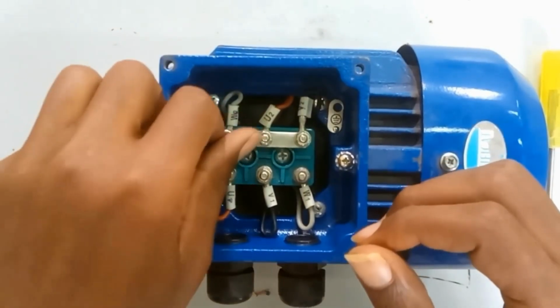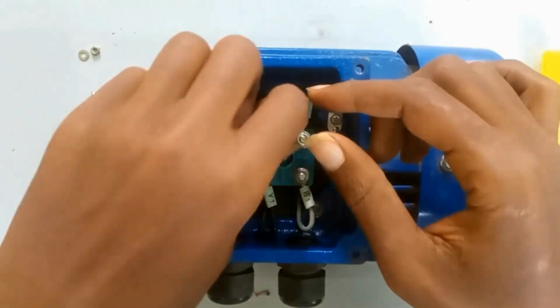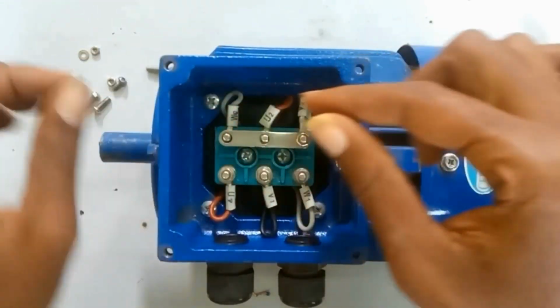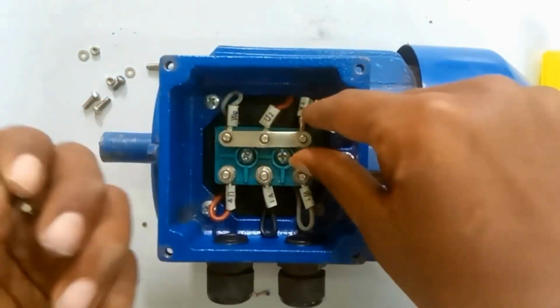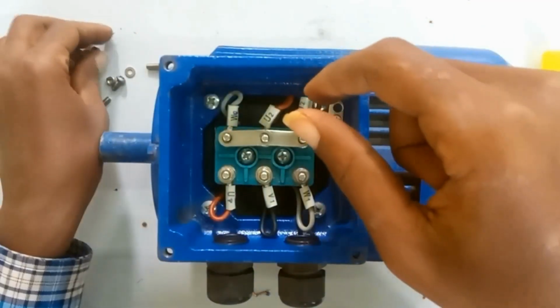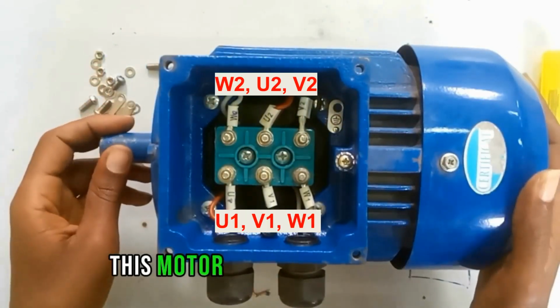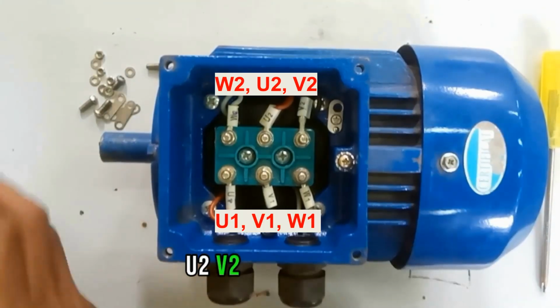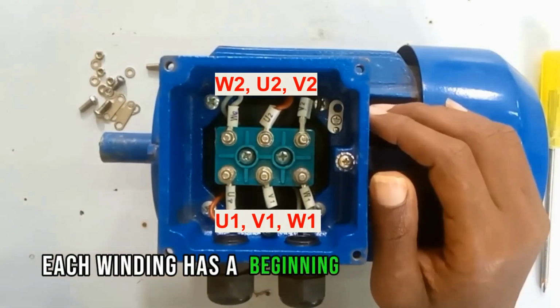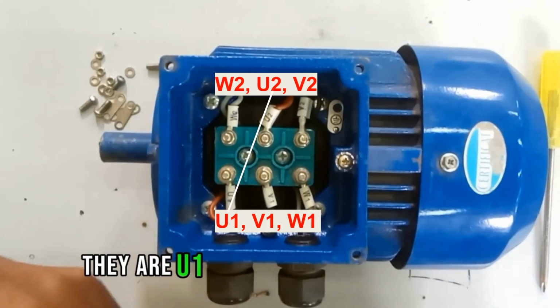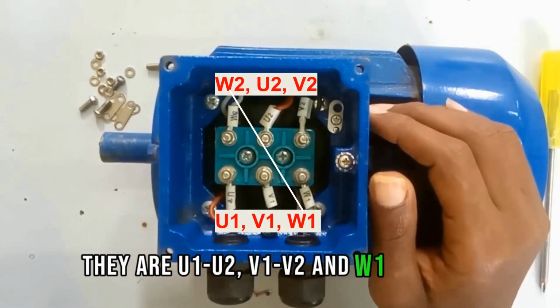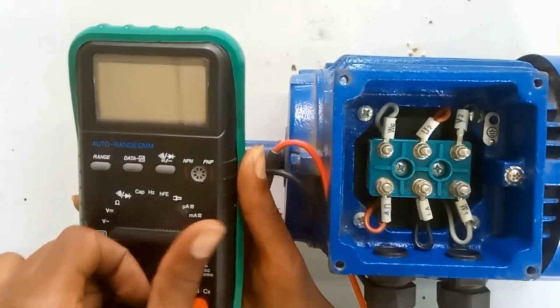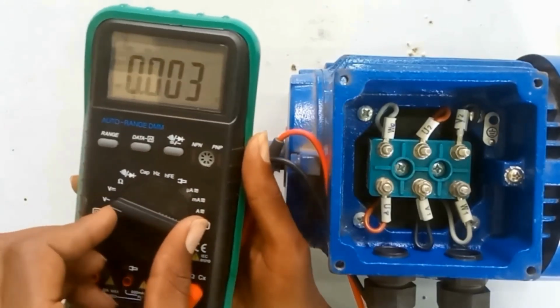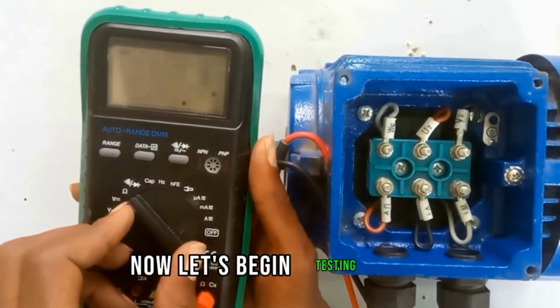Understanding the motor terminals. This motor has 6 terminals: U1, V1, W1, U2, V2, and W2. Each winding has a beginning and an end. They are U1 to U2, V1 to V2, and W1 to W2. Now let's begin testing.